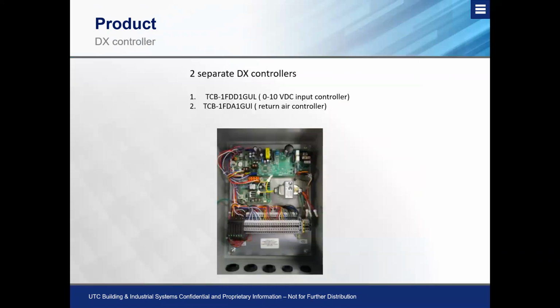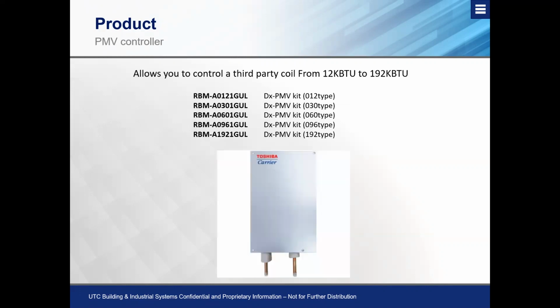As I stated, we have 2 separate DX controllers. The first option works on the 0 to 10 volt DC input, or more commonly works off of the return air. And then of course we need to pair that with a PMV controller or an expansion valve kit to help manage that refrigerant. Again, it will be based on what tonnage coil we're going to need. We get a custom third-party coil that will fit into the existing air handler that we have.